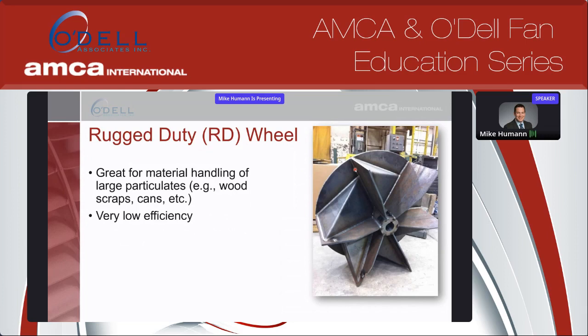So this is really a paddle style wheel here. It's a very heavy duty, rugged duty wheel. You'll see very thick blades, about 3/8 of an inch thick on these, with very heavy gusseting. This wheel rotates from this view in a counterclockwise direction. And this is for heavy material handling.